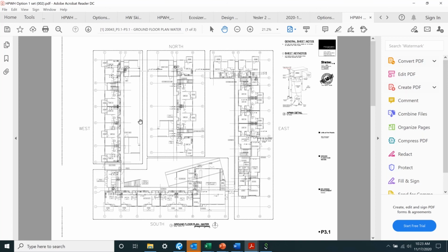You're saying that we would then have to go to resistance heating, and that is really inefficient. Yeah, because the heat pumps just can't squeeze a whole lot more heat out of the air at 40. Some of the 134A manufacturers have some really sophisticated defrost cycles, Colmac being one of them, so they can actually push their heat pump down. But remember, every time you have to melt ice, you're not running the heat pump, so you're also at a loss of capacity as well as derate capacity.